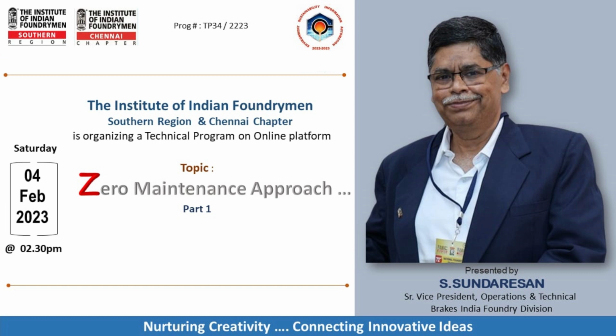For hydraulic oil, normal practice is the supplier would recommend replacement in 1 year or 1.5 years, as the case may be. Initially, when you start your maintenance management system, you just follow whatever the manufacturer says. If they say 1 year, you replace it in 1 year.